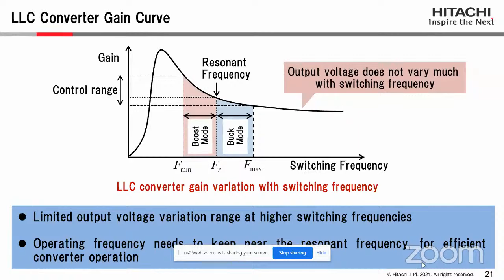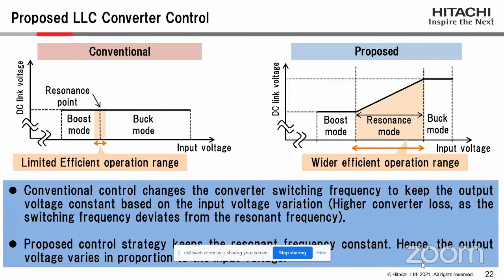So a modified strategy was proposed: the DC converter frequency was kept fixed or varied only over a very narrow range. With the change in input voltage coming from the solar power, the input to the DC bus was changing, so we are basically modulating the DC to AC converter to have a fixed AC voltage. Instead of changing the DC to DC converter frequency to regulate the DC bus voltage, we modulate the DC to AC converter to match the grid voltage demand.